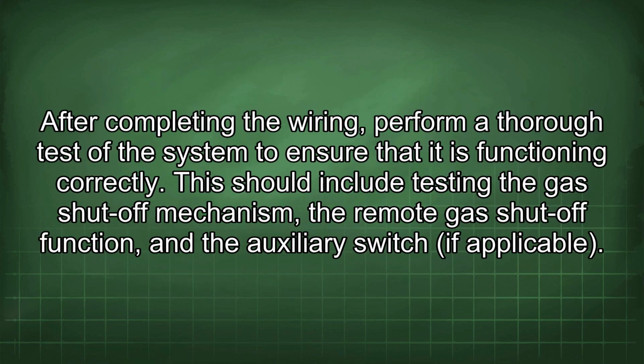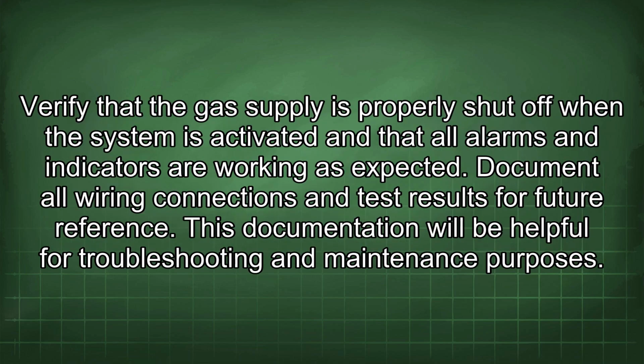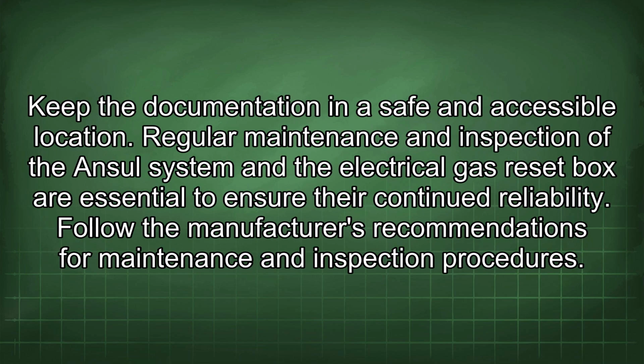After completing the wiring, perform a thorough test of the system to ensure that it is functioning correctly. This should include testing the gas shut-off mechanism, the remote gas shut-off function, and the auxiliary switch if applicable. Verify that the gas supply is properly shut off when the system is activated and that all alarms and indicators are working as expected. Document all wiring connections and test results for future reference. This documentation will be helpful for troubleshooting and maintenance purposes. Keep the documentation in a safe and accessible location.